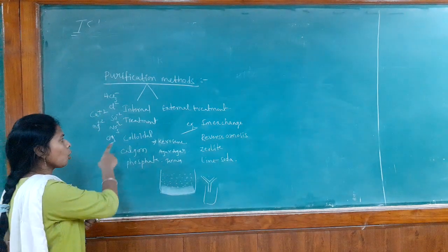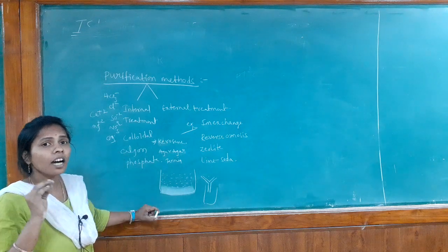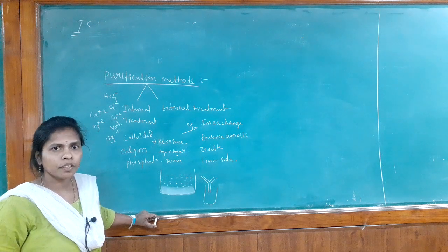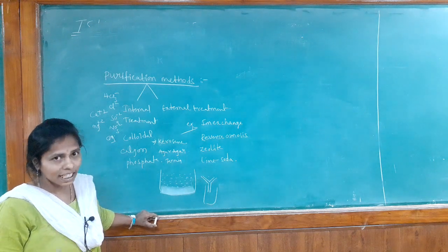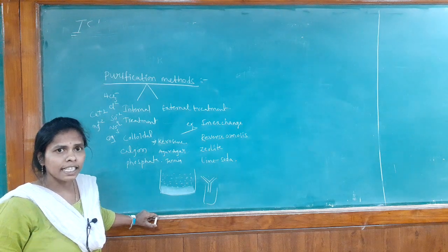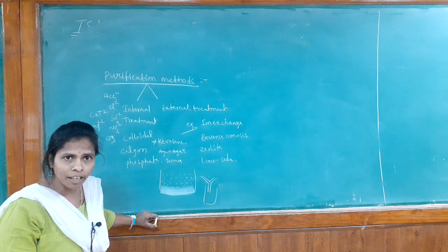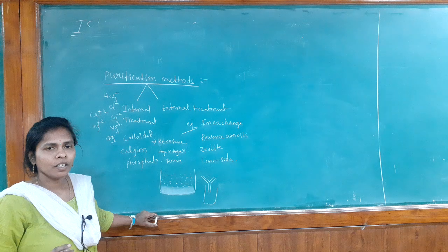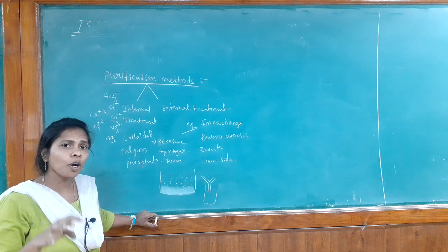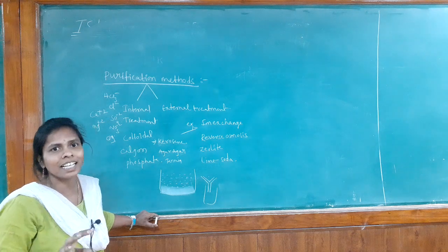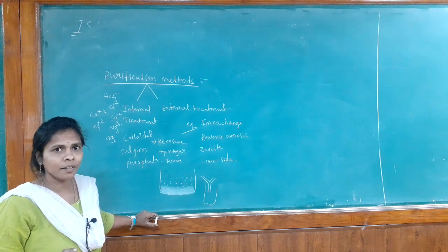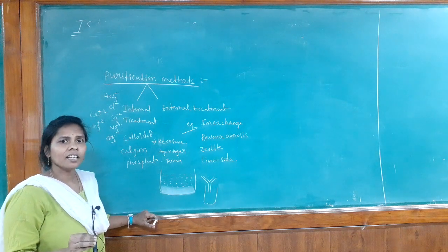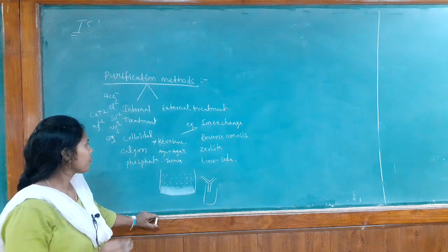Especially these two methods, the colloidal method and the Calgon method, are used in boiler treatments. We know what the boiler troubles are, we know how scales form and how sludges form. Here the scales form especially due to the presence of calcium containing salts. You know how the scales stick to the boiler material. Due to the scales sticking to the boiler material, the boiler efficiency decreases. The boiler lifetime also decreases due to the formation of scales. So, especially these methods are useful for boilers.